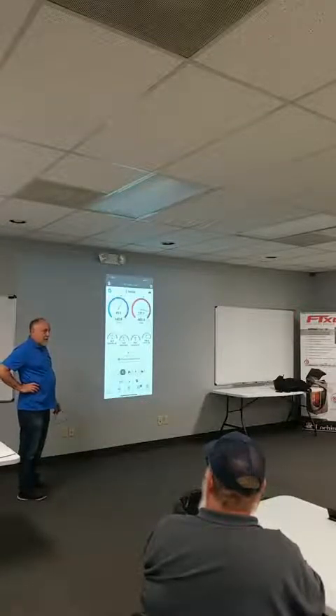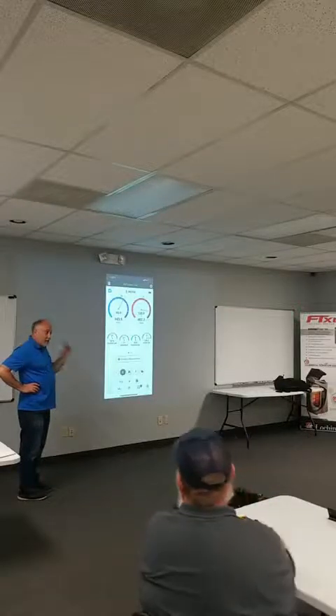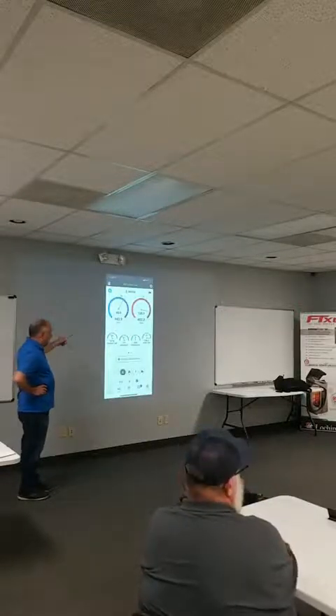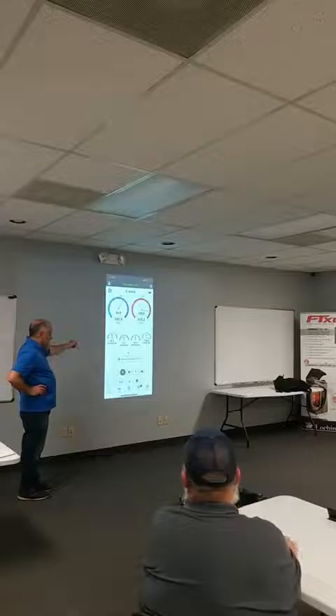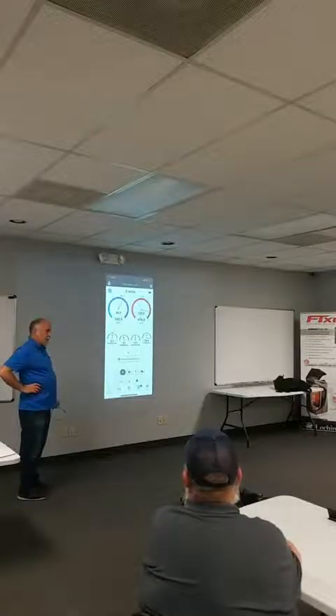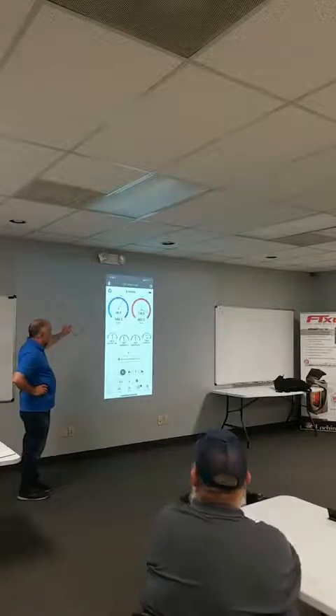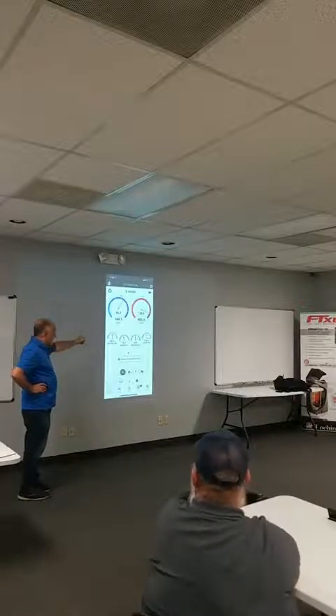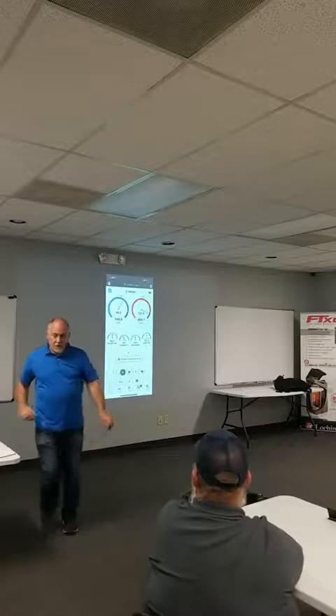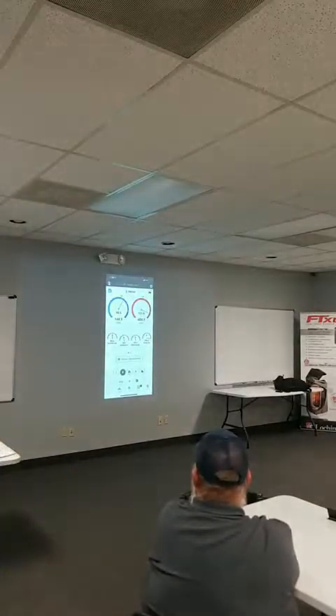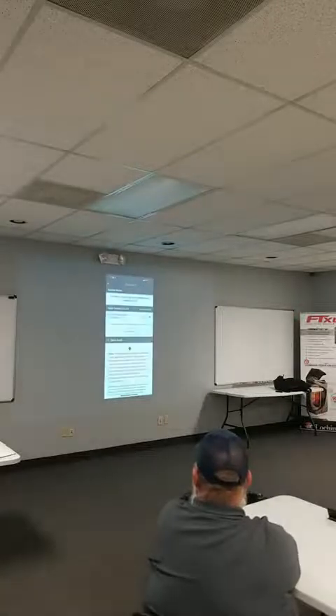So MeasureQuick really can't evaluate a system until it's stable. Now what's the TXV doing? It's closing back down because it's saying, I'm not going to overflood my evaporator, so it's throttling back down. Eventually what we're going to get is just an overcharge. So we have a high liquid line temperature, and we're also going to have a high approach temperature now. So we click on approach, and these are all symptoms of a dirty condenser.